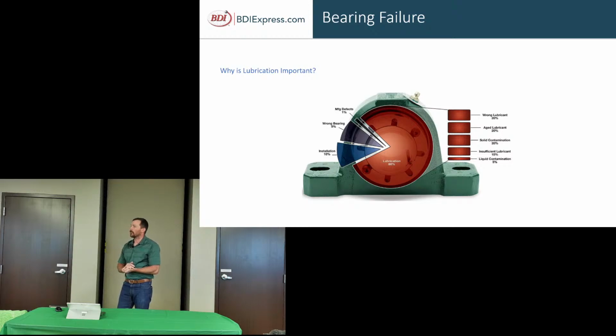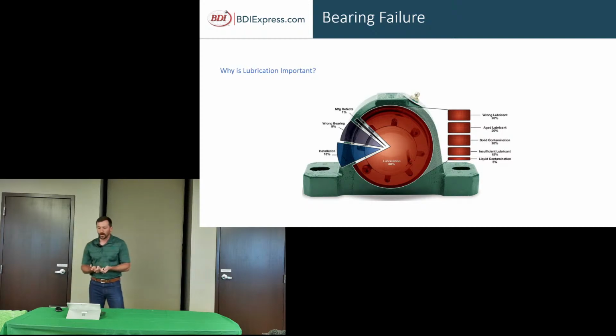So I said heat's an enemy, but lubrication is the number one cause of bearing failure. They say 1% is coming from manufacturer defects. I know we all like to blame it more on the manufacturer than the lubrication and other causes of failures, but lubrication is the number one cause of failures, and that's going to be from the wrong lubrication. Do you guys all have separate greases for your motors and your bearings? Mounted bearings? I want to see everybody shake their head yes. Do not mix the two.